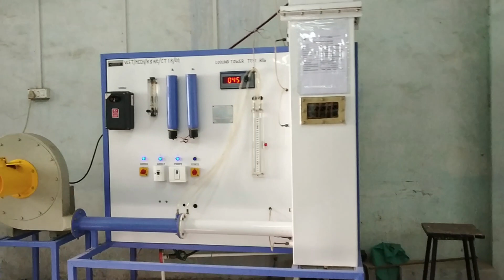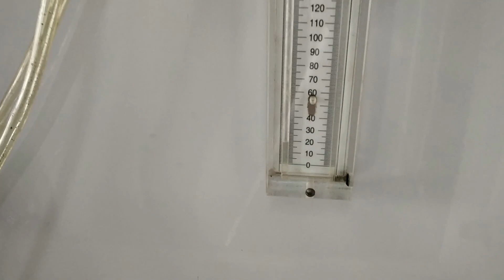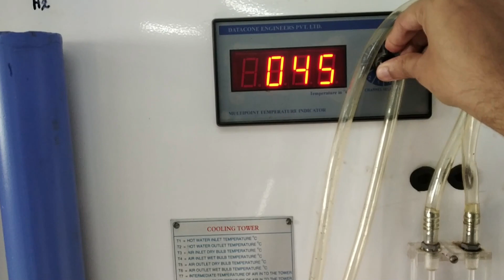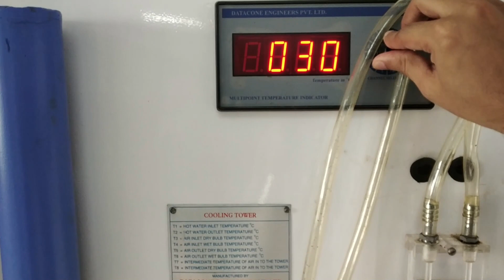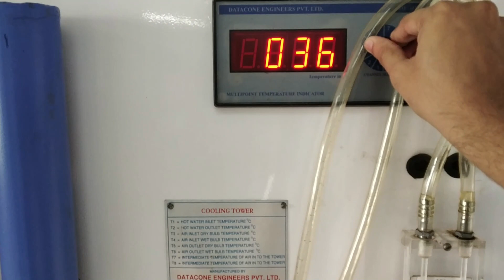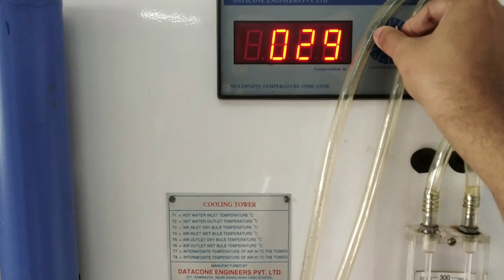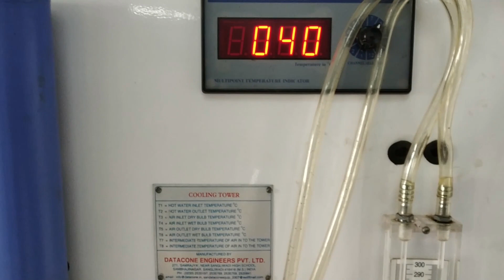Now we will take reading number 3. So LPM is the same, 4 LPM. And the manometer difference is 300 on the top side and on the bottom side we have 20. We'll take the temperature values. T1 is 45, T2 30, T3 30, T4 30, T5 35, T6 34, T7 29, T8 40. Again we have to wait for 10 minutes.